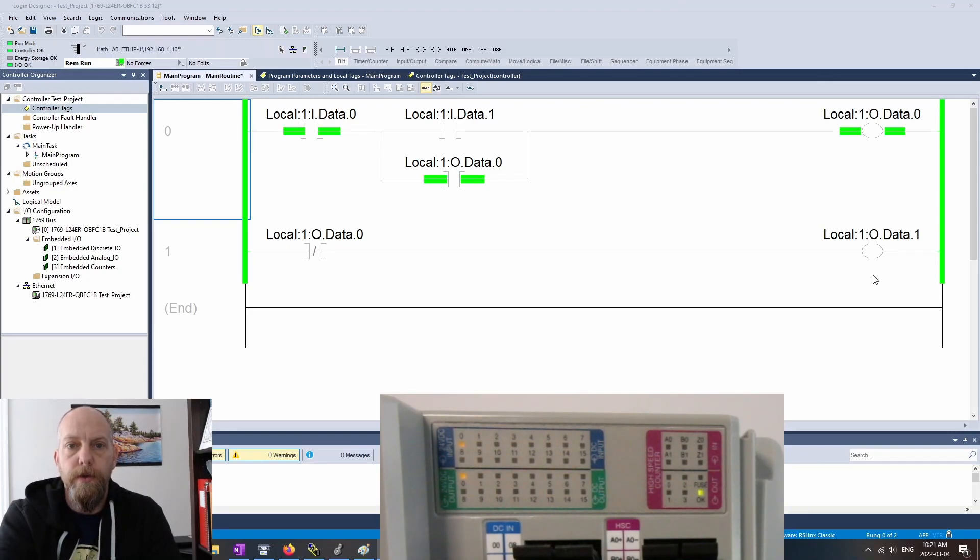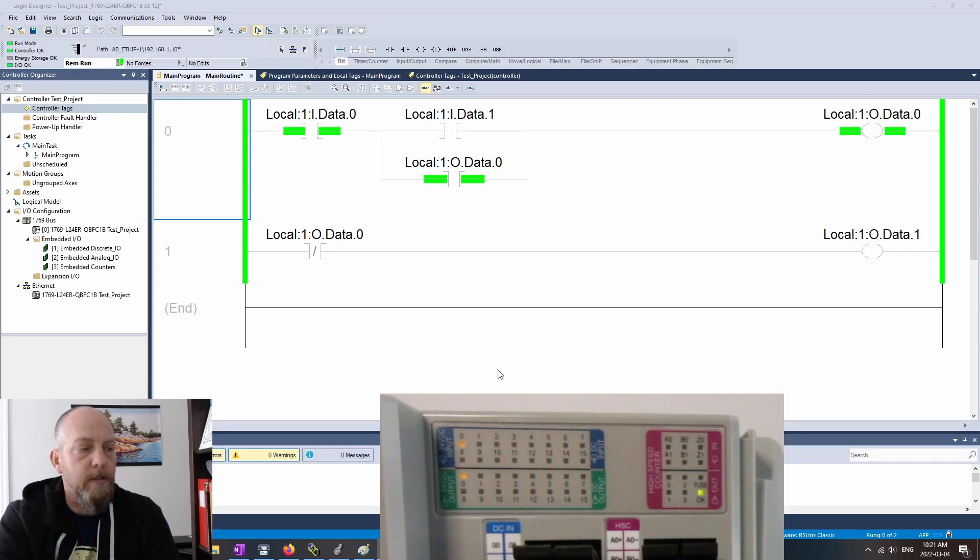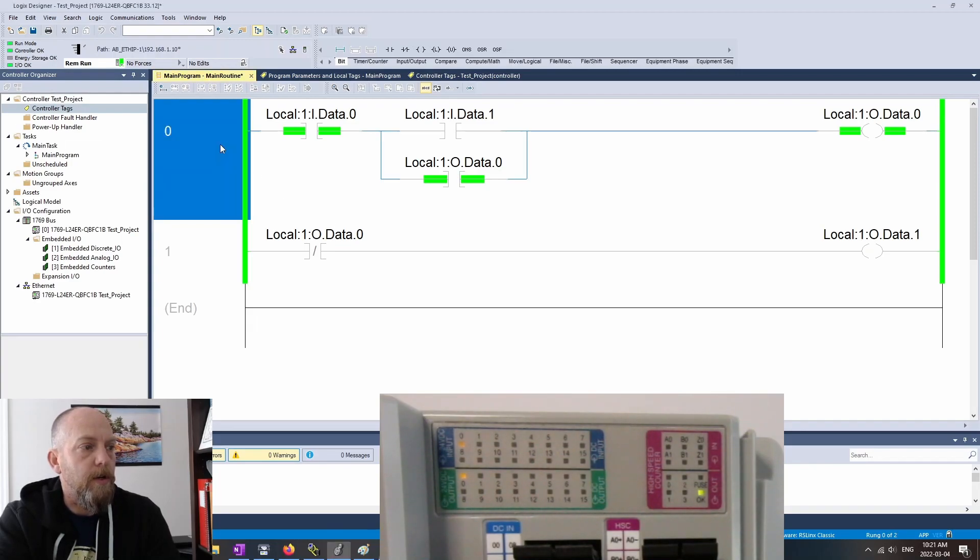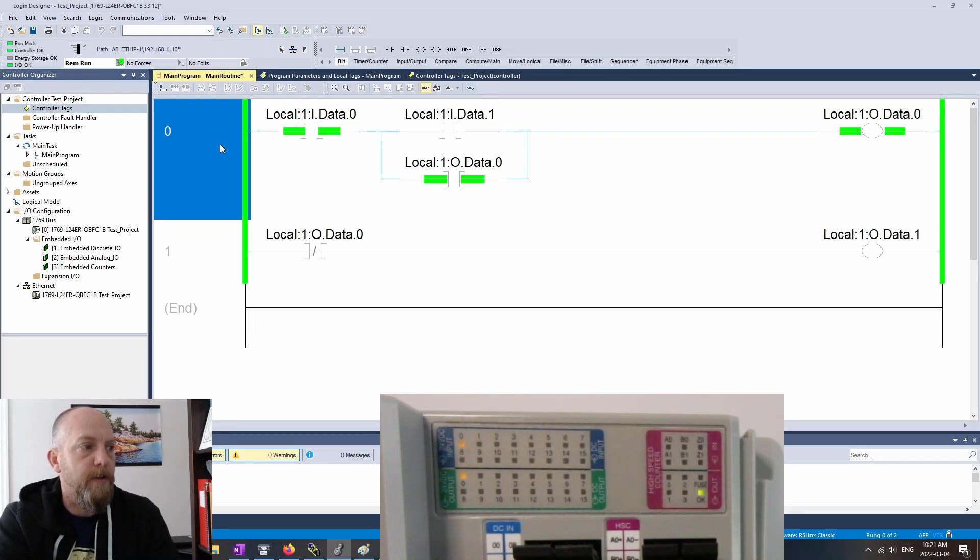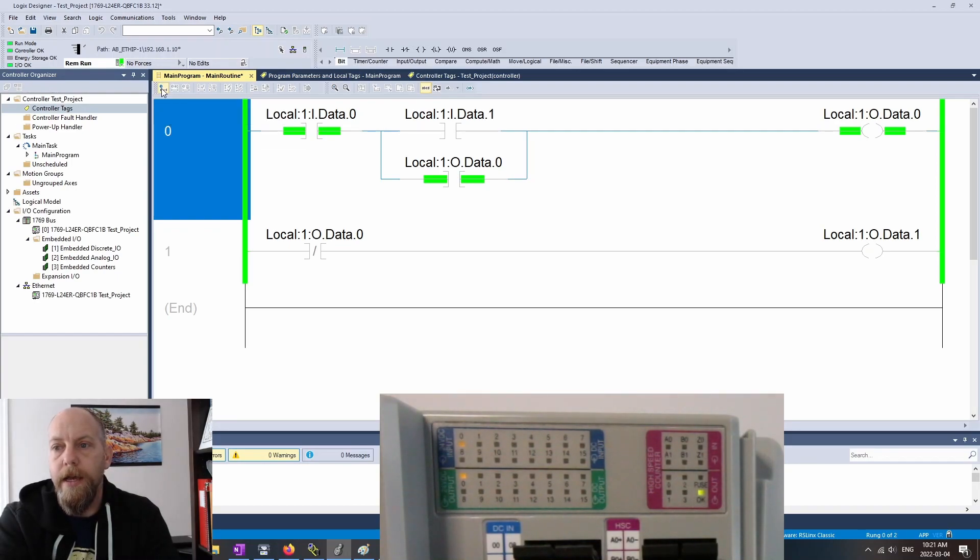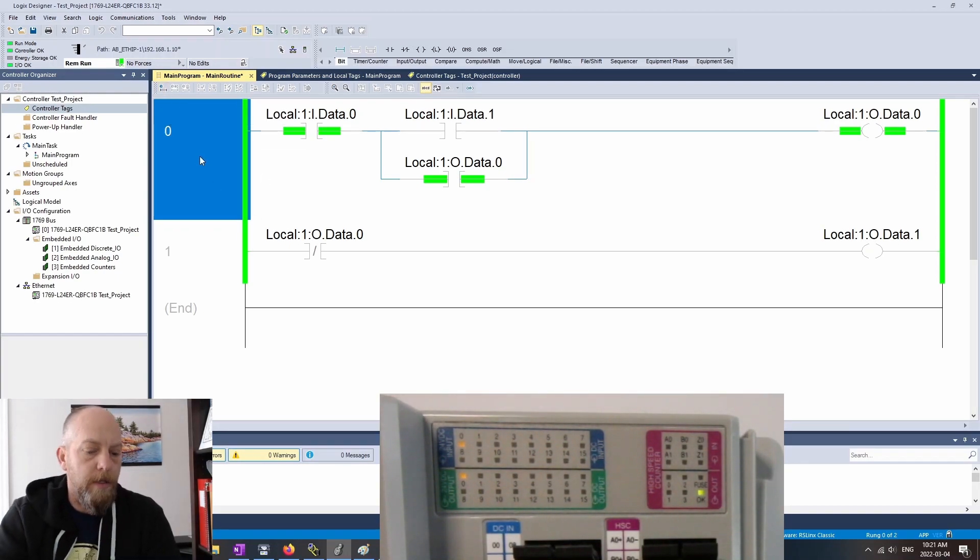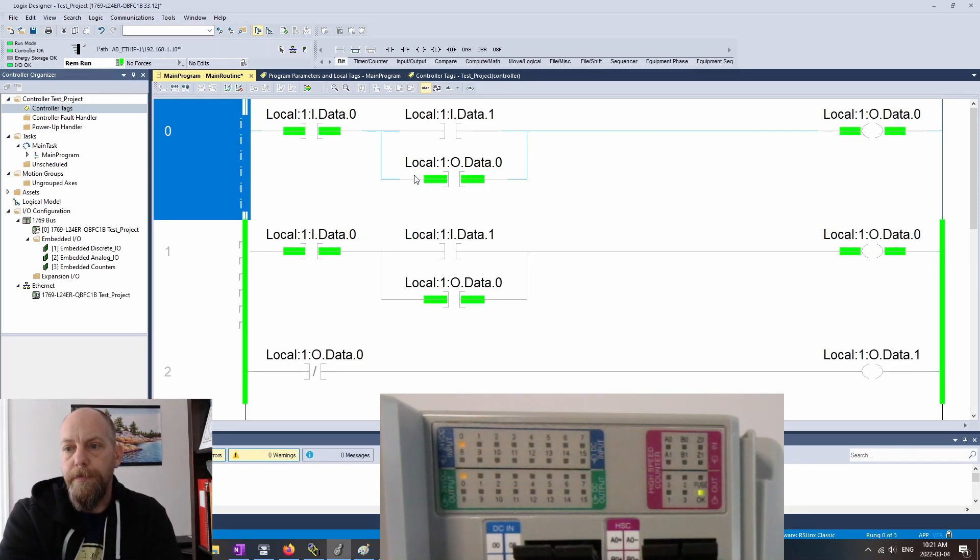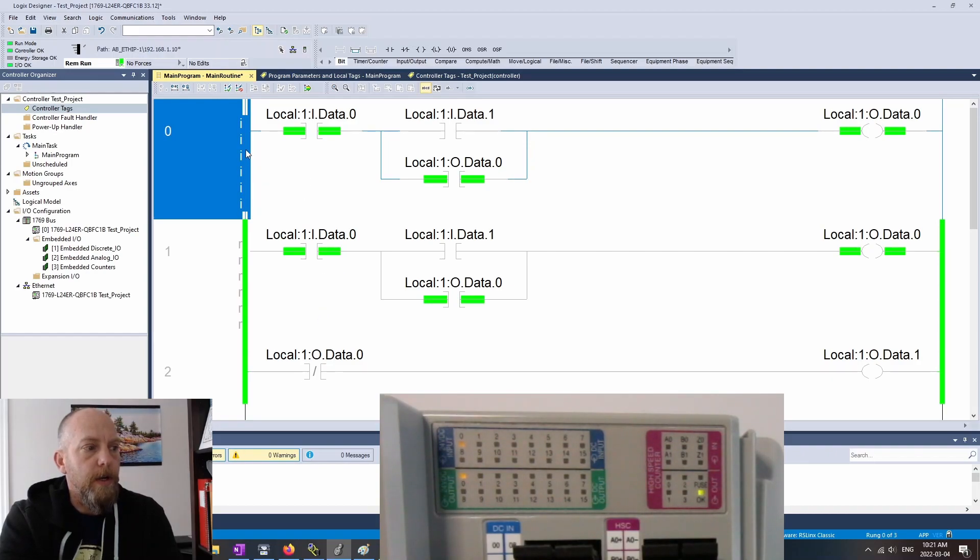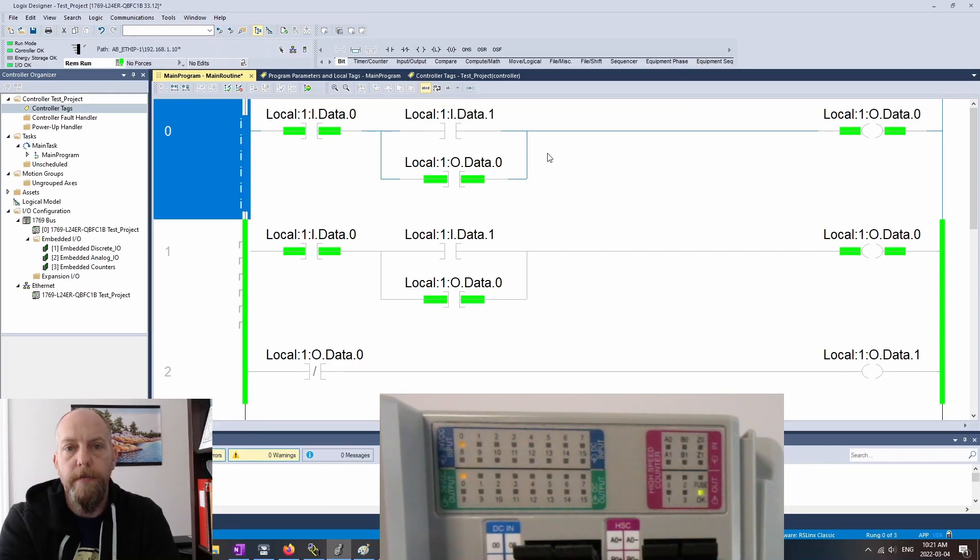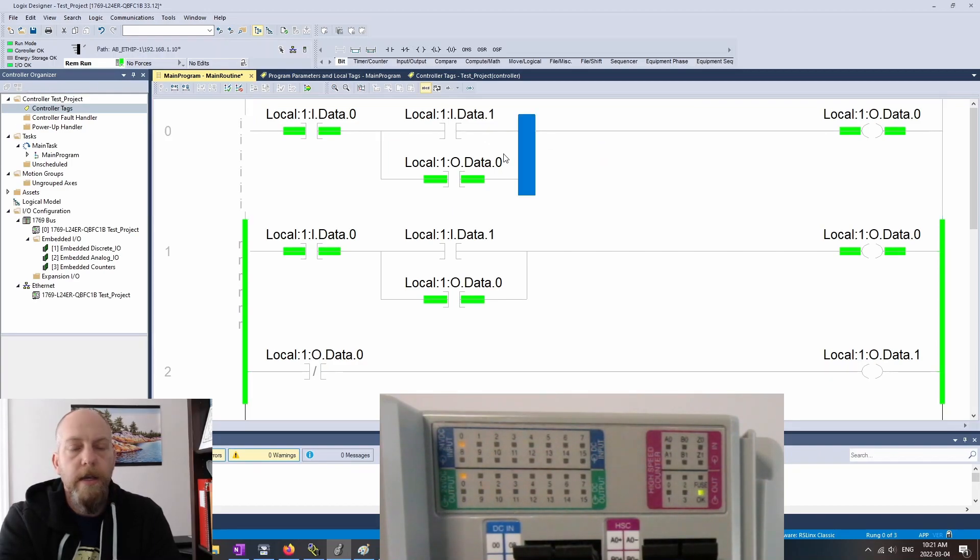Let's go through the online edits now and see what happens with the rest of the outputs as we change, as we add in some stuff. So here, I'm going to click on this rung right here. Remember that we said in the previous video, you can do up here, you can click on this start pending rung edits, or you can hit Ctrl Shift S, or you can click on this guy and then just hit enter. Now we've got two identical rungs here. One is the insertion rung, one is the replacement rung. So it's going to replace our existing code and insert our changes from this rung right here.